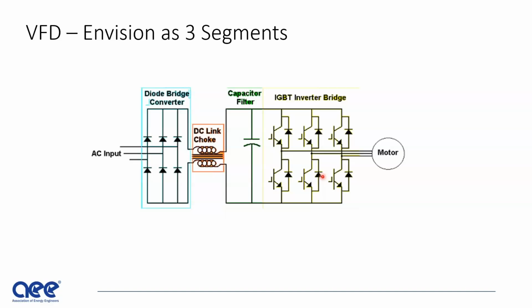So you can envision a VFD in 3 segments. You have your diode bridge. It could be an active bridge with SCRs. You have your DC choke and capacitor for your filter. And then you have your IGBT bridge, that's insulated gate bipolar transistor inverter bridge. Here you see a 6 pulse. You also have 12, 18, 24 pulse inverters. They even go higher than that. As you get higher and higher in power levels, you want more and more pulses, and I'll show you why here in a bit.